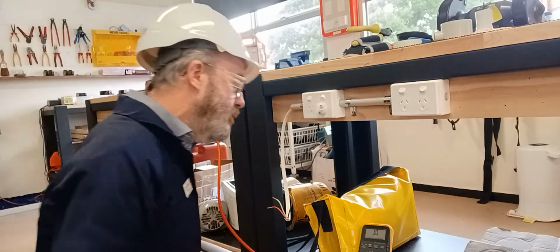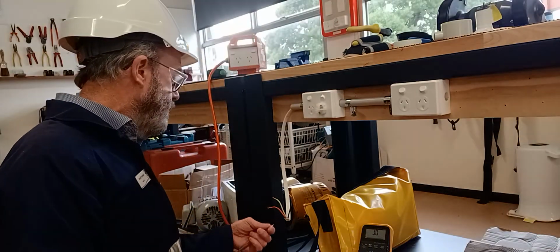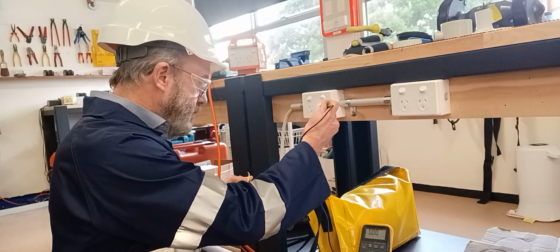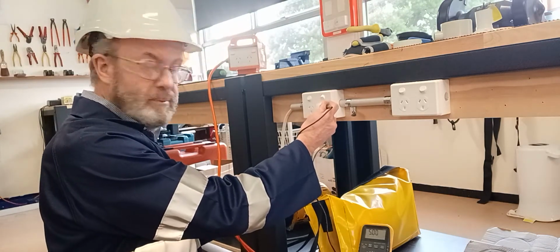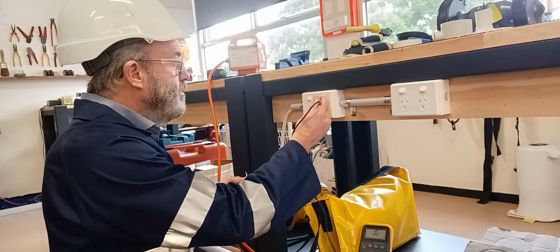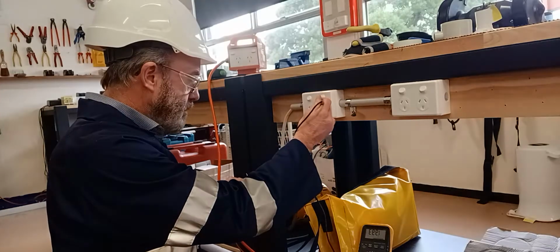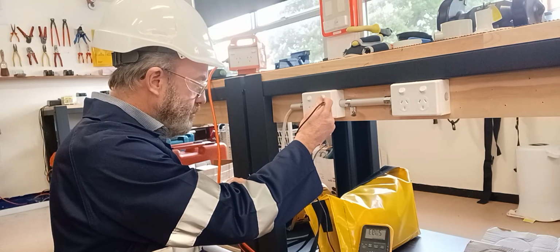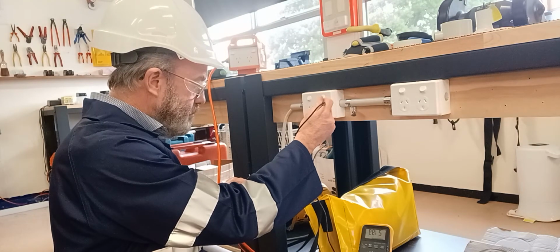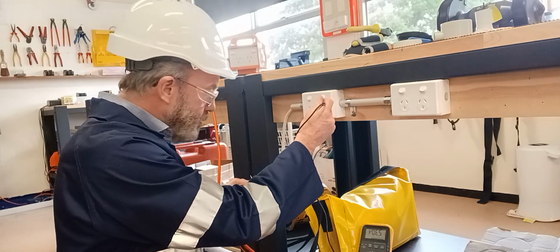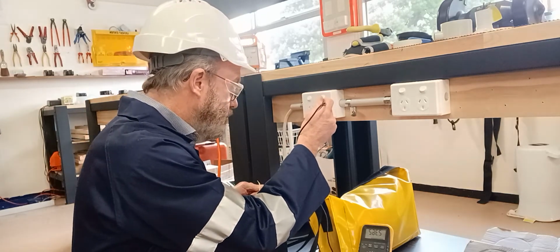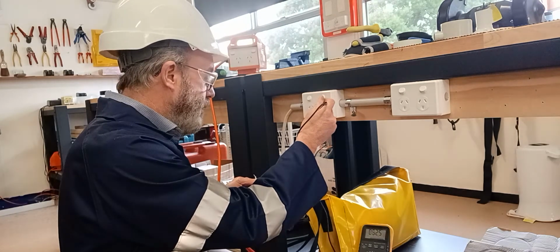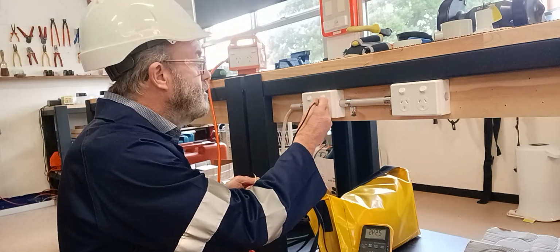Okay, so the first test is active to active pin. Okay, here we go. Active to active. The switch turned on, I'm getting a reading of 0. Switch turned off, I'm getting a reading, basically, it's close to infinite. It's 2.2 megaohms, which is quite a lot. And that's pretty close to what it should be.